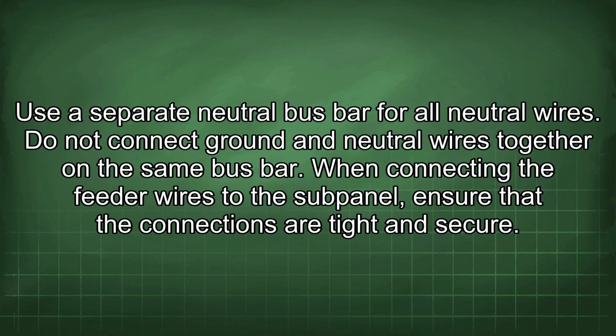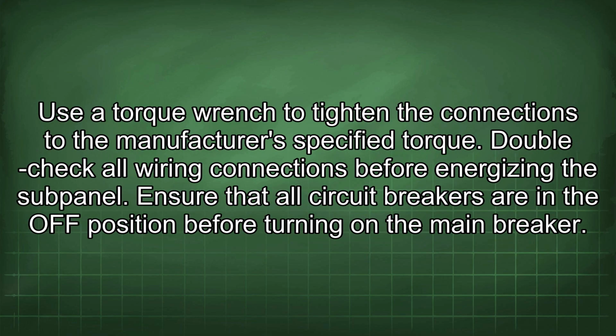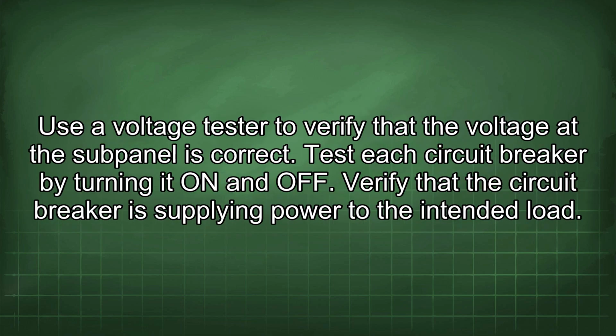When connecting the feeder wires to the subpanel, ensure that the connections are tight and secure. Use a torque wrench to tighten the connections to the manufacturer's specified torque. Double check all wiring connections before energizing the subpanel. Ensure that all circuit breakers are in the OFF position before turning on the main breaker. Use a voltage tester to verify that the voltage at the subpanel is correct. Test each circuit breaker by turning it on and off. Verify that the circuit breaker is supplying power to the intended load.